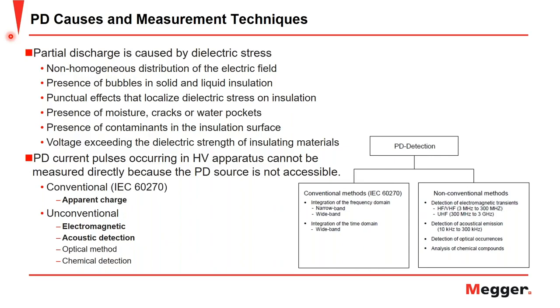And when we talk about measurement techniques, the partial discharge current pulses occurring within the high voltage apparatus cannot be measured directly because the PD source is not accessible. So therefore, there are many different means of measuring PD activity. And they are broken into conventional and unconventional methods. The conventional method is covered by the IEC 60270 standard that was mentioned previously, where the partial discharge as apparent charge is measured in picocoulombs. And then you have your unconventional methods, and that can range anywhere from electromagnetic detection to acoustic detection, optical detection, and even chemical detection. Here I have bolded the electromagnetic and acoustic detection because they are two of the more popular methods and will be discussed in this presentation.